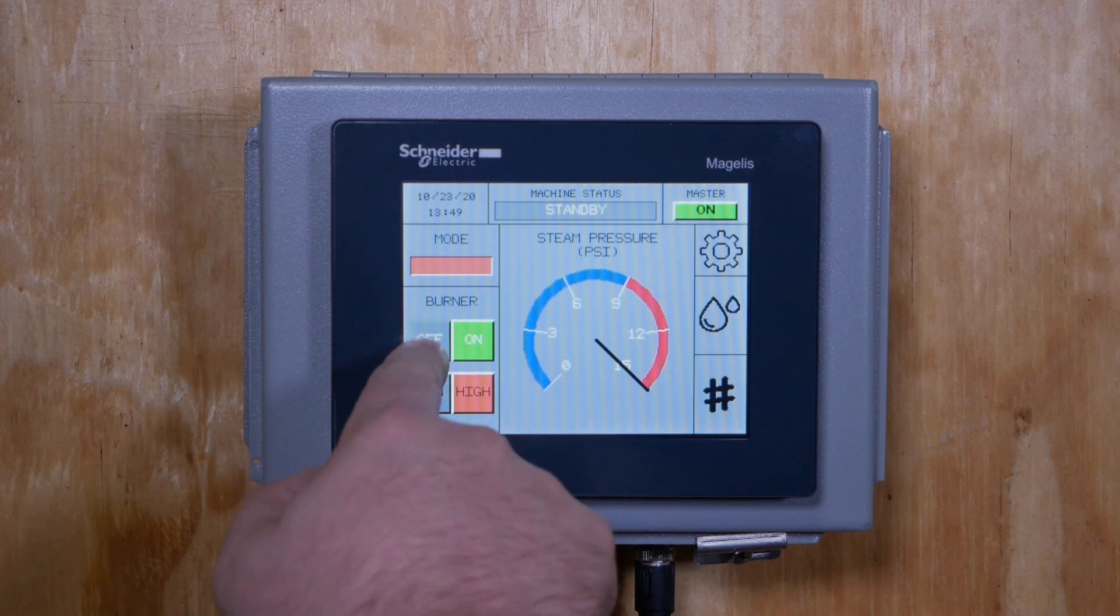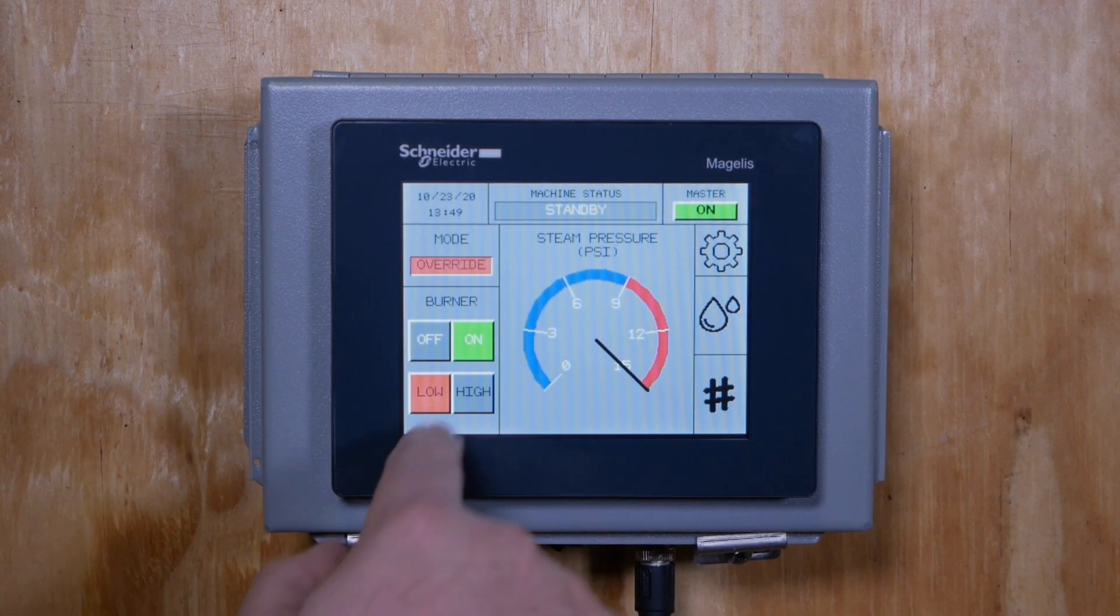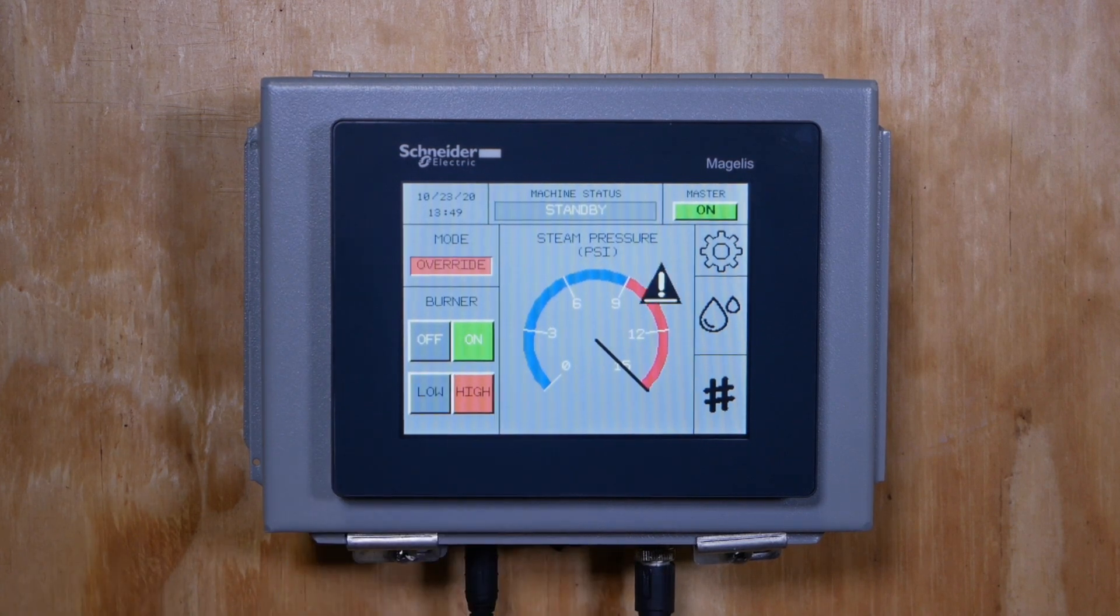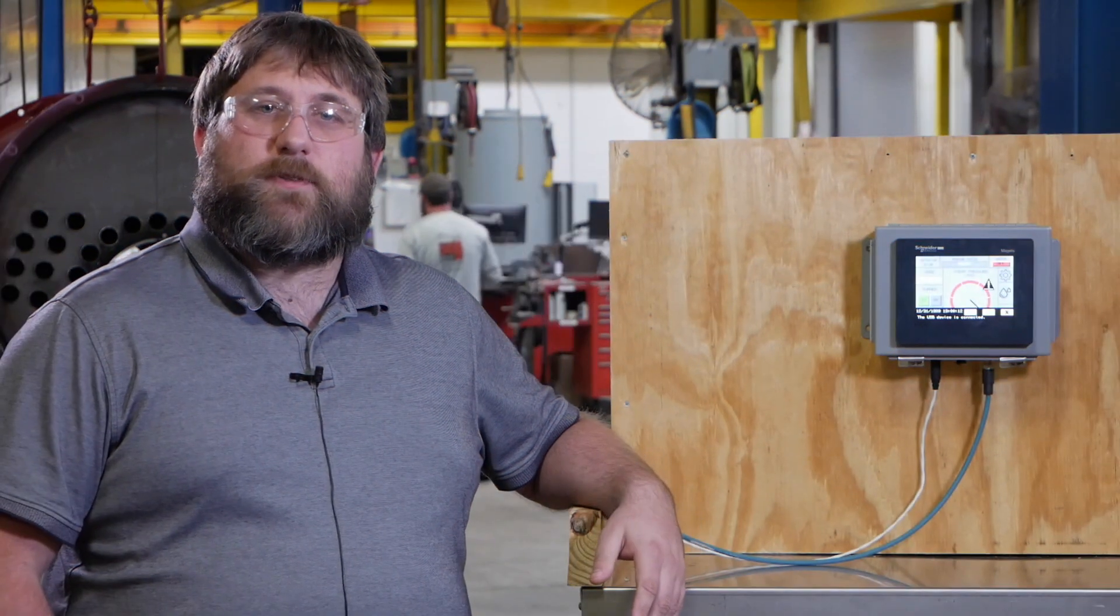Lastly, the burner status displays burner parameters. When you are in override mode, additional controls are unlocked allowing you to turn the burner on and off and change between low and high firing modes. Now that we've covered the home screen, let's dive into the settings menu.